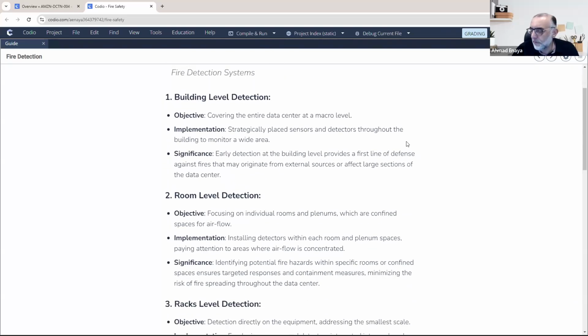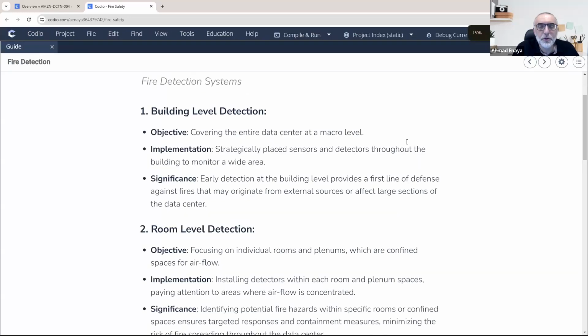There are different levels to consider when it comes to fire detection. First, as in any business or location, we should have building-level detection, meaning a strategy or procedure to detect fire in the building, in the normal NOC center, and wherever we have employees. This technology or procedure is the same as in any business: we should have something at the building level to detect smoke, heat, and flame. It should be installed all over the building, integrated into the BMS, the building management system, and it should definitely be monitored.